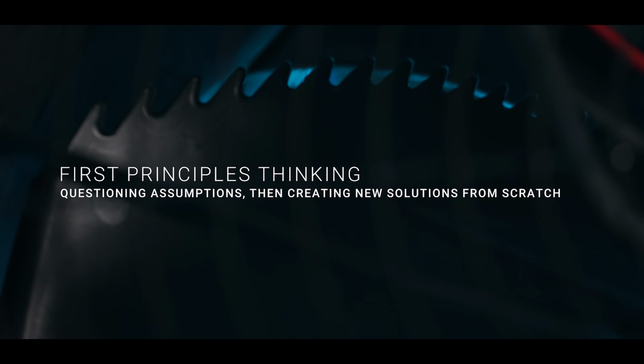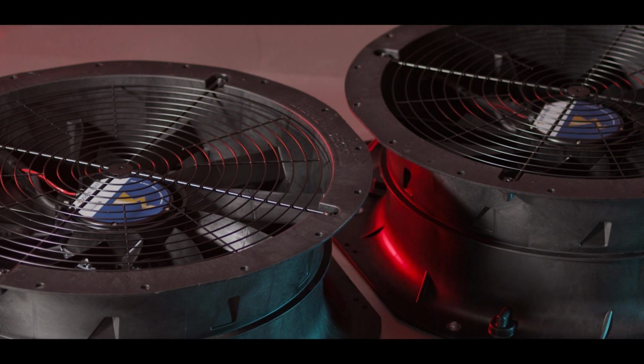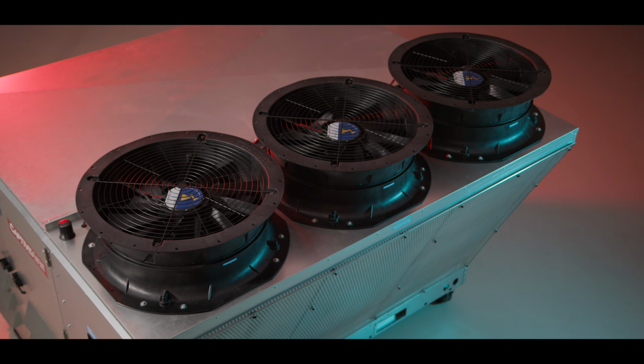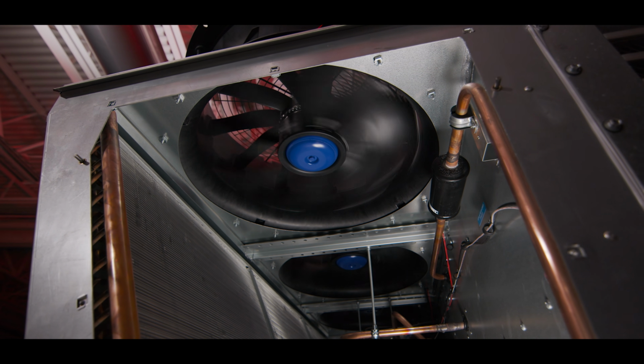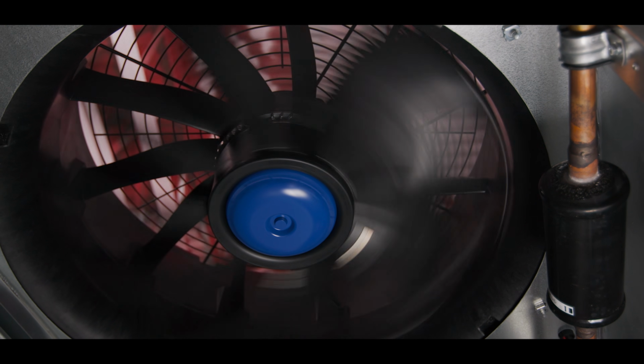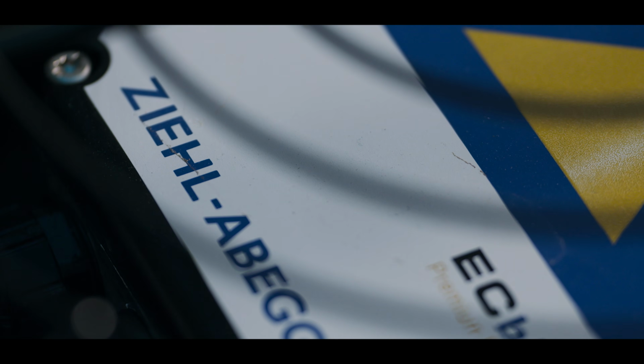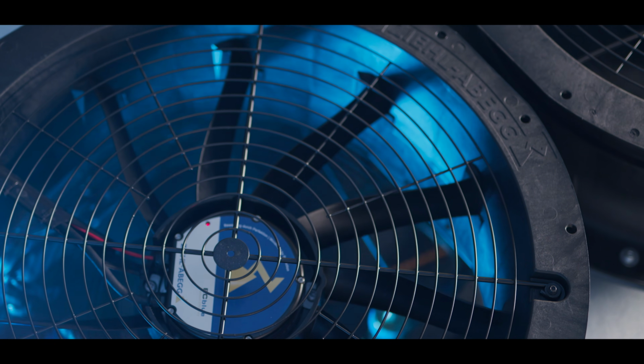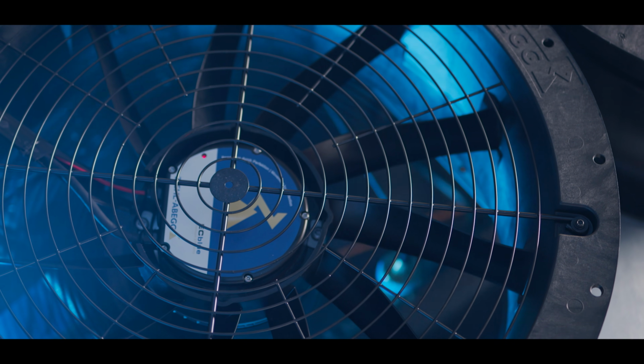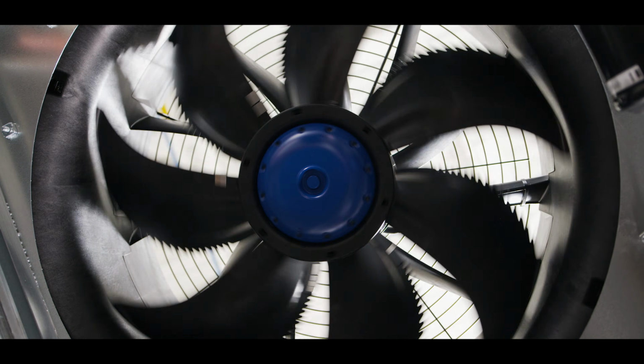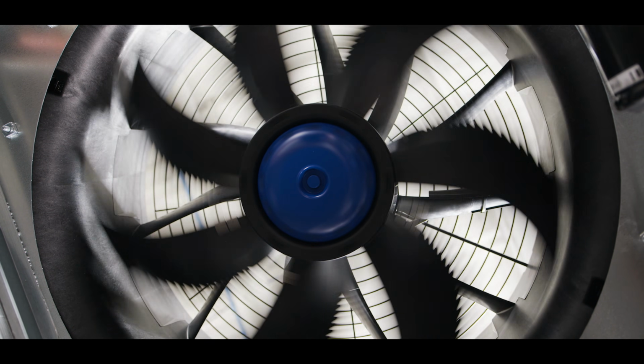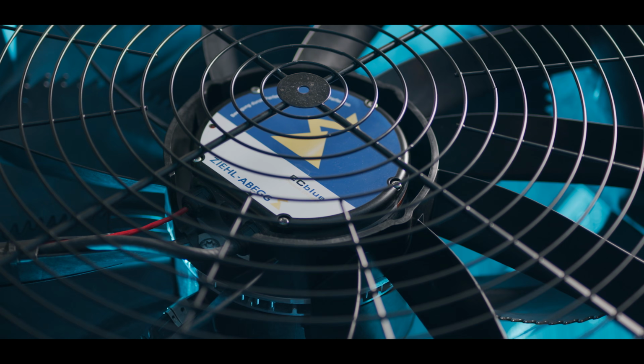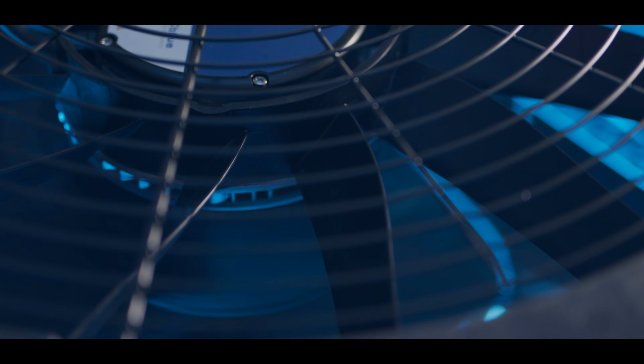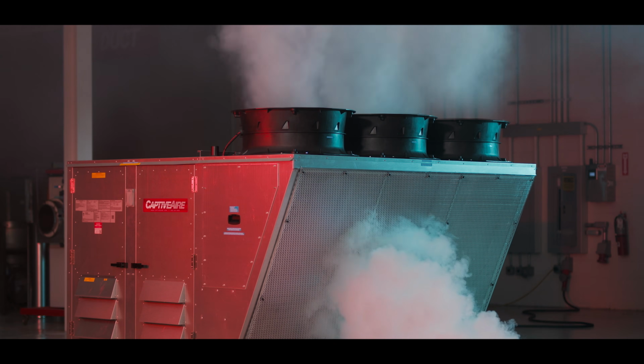We start to look at other manufacturers, other equipment, and then you go, I wonder, this is used in this application, but it's really the same as what I'm trying to do. We standardize on a high-end EC motor condensing fan, very low noise, and it made a world of difference for the overall unit performance. Every single fan essentially has a VFD, a variable frequency drive, that's tuned to that specific motor in that housing. And what that does is it allows us to use the most efficient combination of propeller, motor, and housing. There's static blades on the leading edge of those fans that help to straighten the airflow patterns, ultimately reducing the energy required.